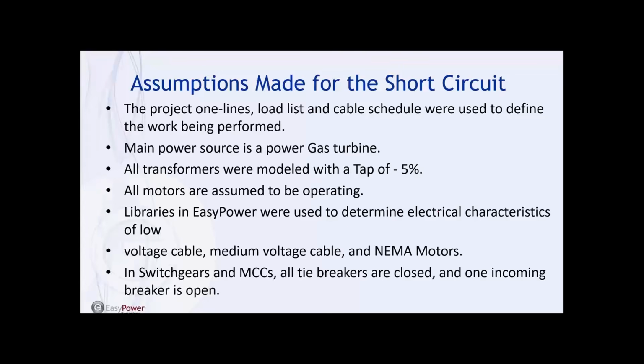We used information from the library in EasyPower, and we were able to modify the harmonic content on some loads as well. As I said, switchgears and MCC, all tie breakers are closed. We have only one incomer open.